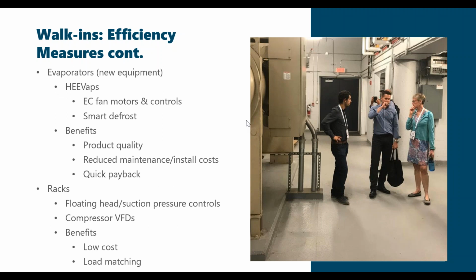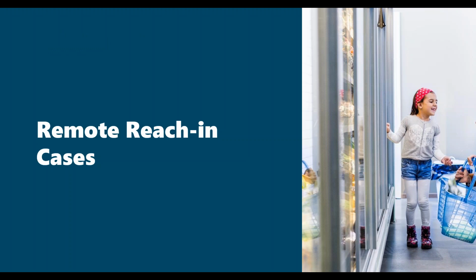And so then with the rack systems, as we're talking about it with customers, this is a whole bigger efficiency measure that we won't really get into right now because there's just so many opportunities with rack systems. Some of the big ones that we've worked with our customers with have been the floating head and suction pressure controls. So reducing the lift on the compressor by adjusting some of the suction and head pressure set points. And then adding VFDs to both compressors and condensers when they're separate in a rack system like this, and controlling the speed of those, the fan and the compressor motor, to better match the refrigeration load in the system. But there are a lot of other measures that we can talk about in detail, kind of offline. So next slide, please. So now we're moving into the remote refrigerated cases. So these are what you would see on the sales floor.